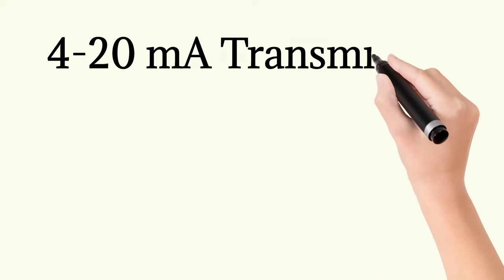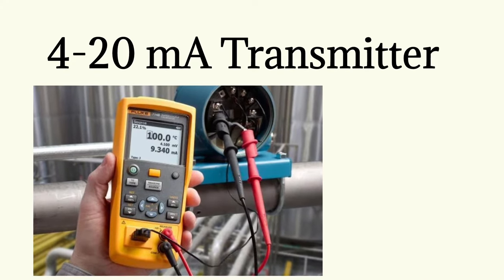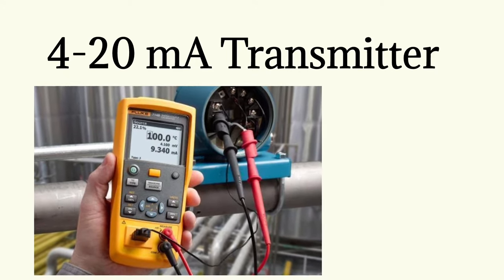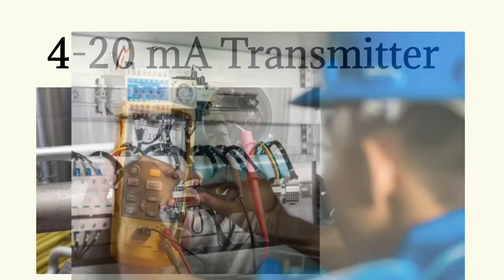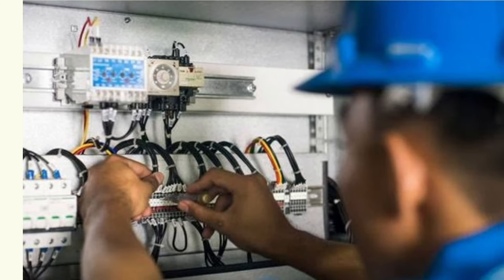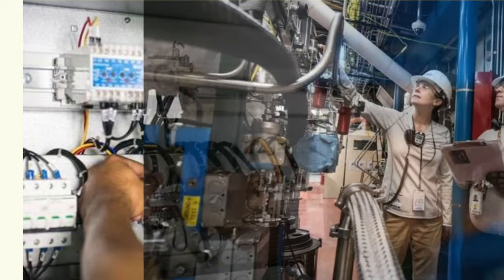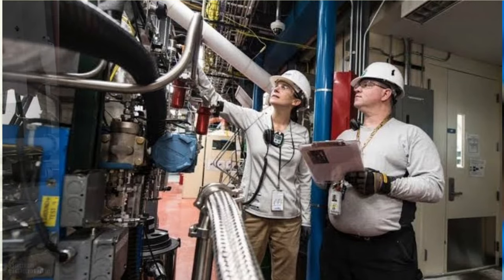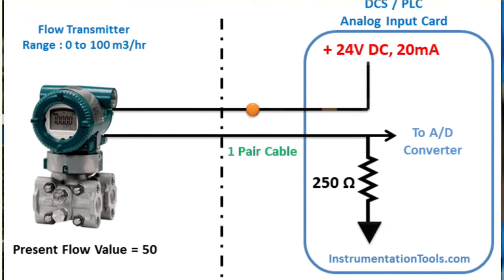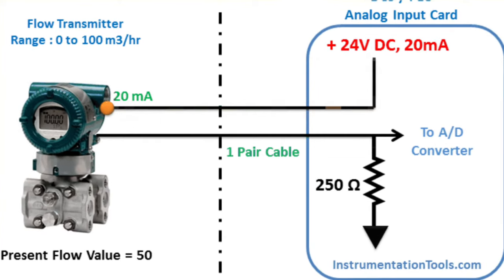A transmitter is a transducer that responds to a measured variable by means of a sensing element and converts it to a standardized transmission signal, like 4 to 20 milliampere, that is a function only of the measured variable. Transmitters can have any of several electrical connection schemes. The most common and easiest to use is the two-wire, loop-powered configuration. This is generally the basic configuration for industrial process control systems when digital communication is not required.